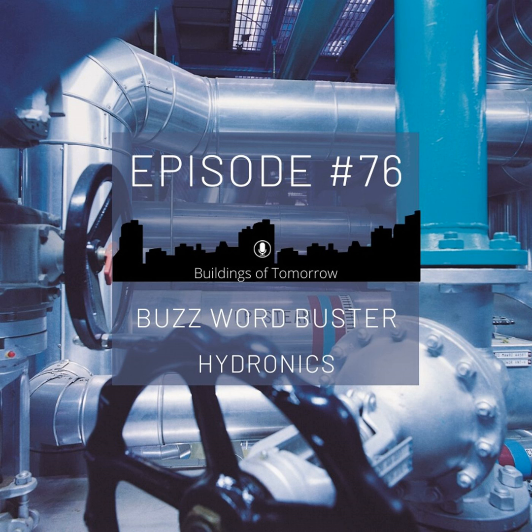And that, of course, is a big change, and it is a fundamental law in our hydronic circuits, because based on that, the power consumption also goes down dramatically. Here the theory says it goes down by the power of 3, which is a little bit too optimistic, but in a lot of cases, it goes down dramatically by more than the square, or close to the power of 3. So that's why we should really focus on these proportional laws. They are basically the reasons why we have variable speed drives, and why we have EC motors in pumps and fans, so that we can control the speed to really work with these laws and get as much as possible out of them.